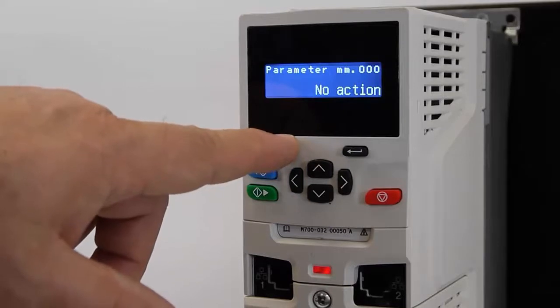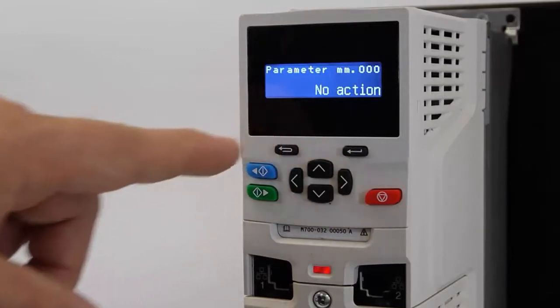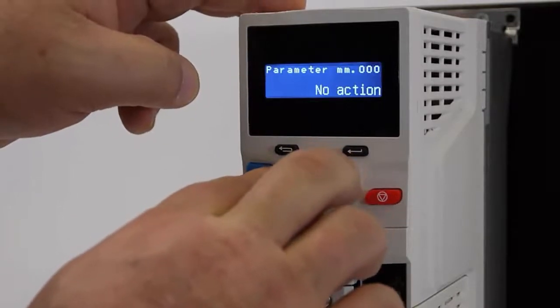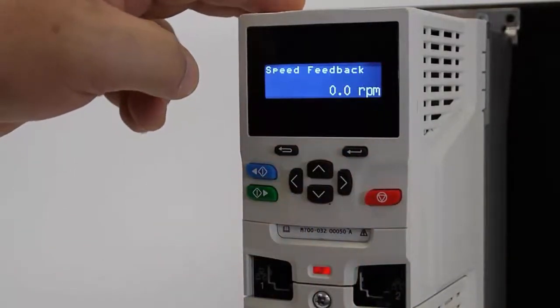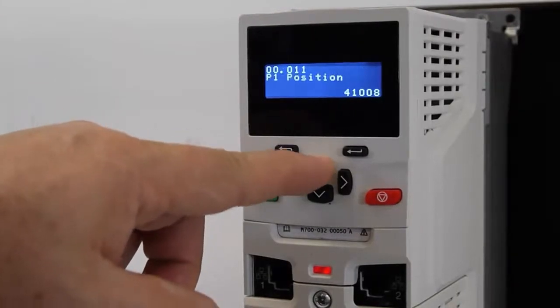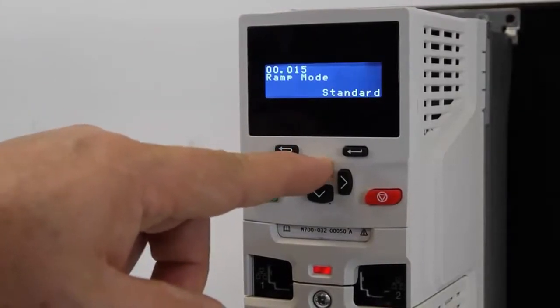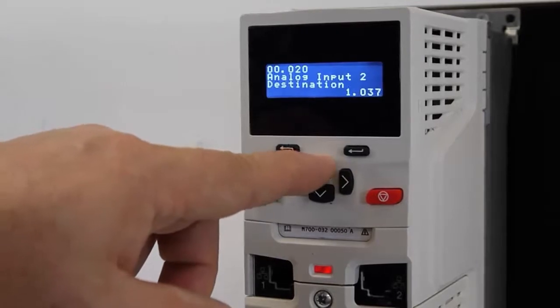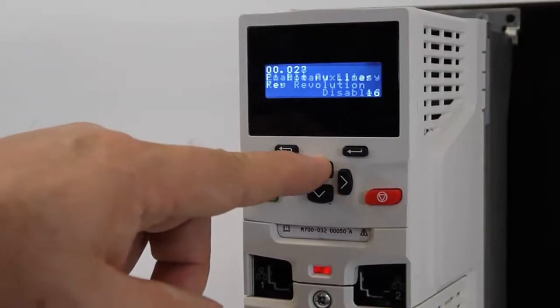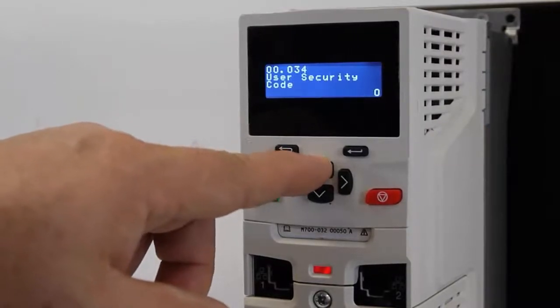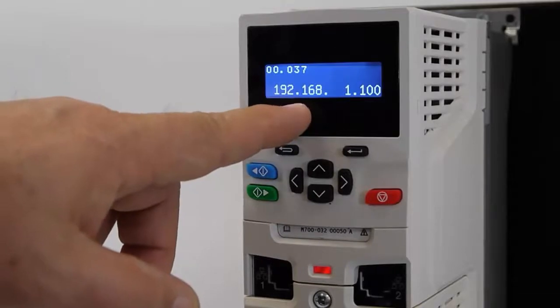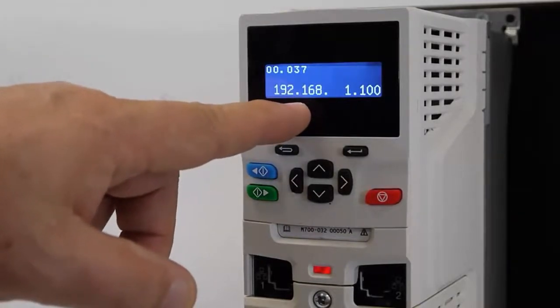I'm going to verify the settings by going to menu 0, parameter 37. I'll press the outer two arrows to get back to menu 0 quickly, then use the up arrow to check that my new IP address has taken effect — that's menu 0, parameter 37. And there it is. We've successfully created an IP address in this drive.